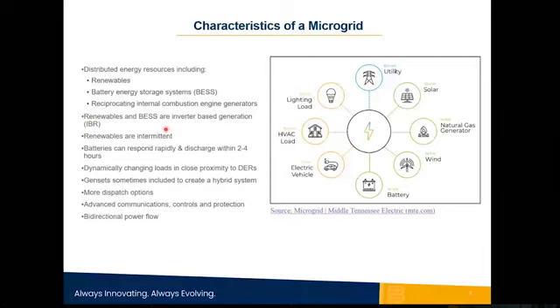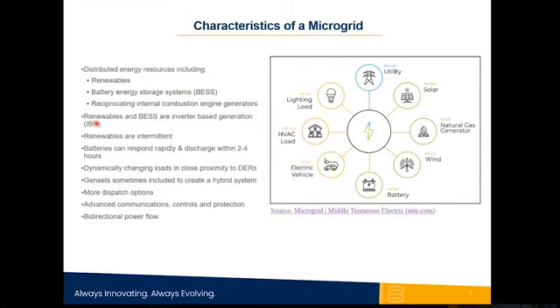Renewables and BESS systems are inverter-based generation. The reason for that is because they generate a DC output, and that DC has to be converted to AC because our power system is an AC power system. So that DC has to be converted, and as a result of that, an inverter is needed to do that. So that's why they're called inverter-based generation, IBRs.